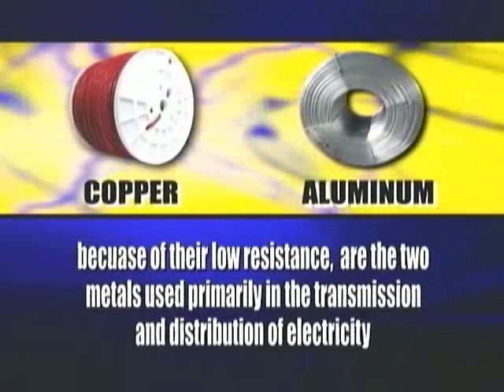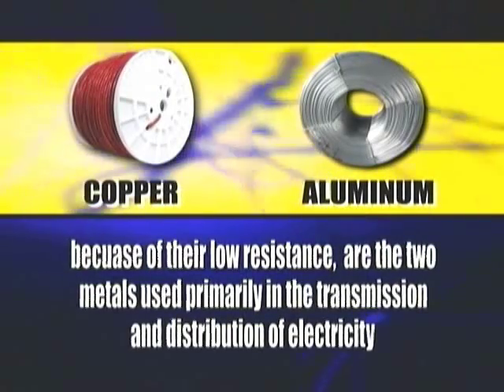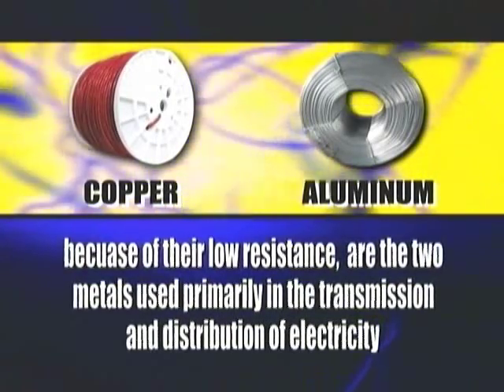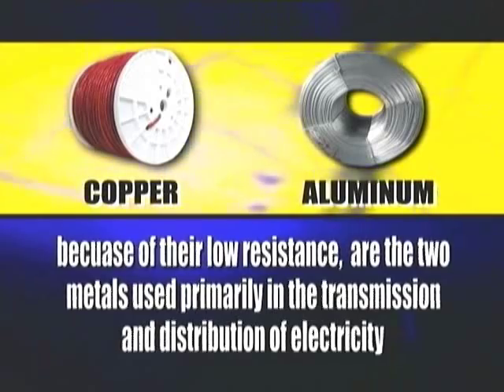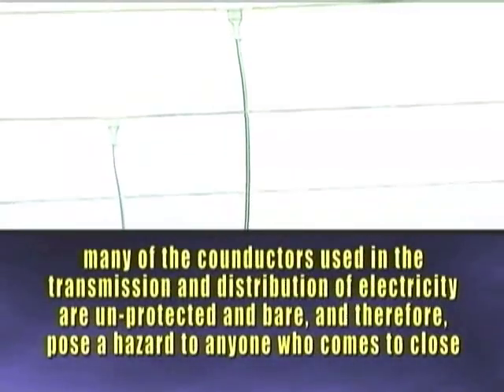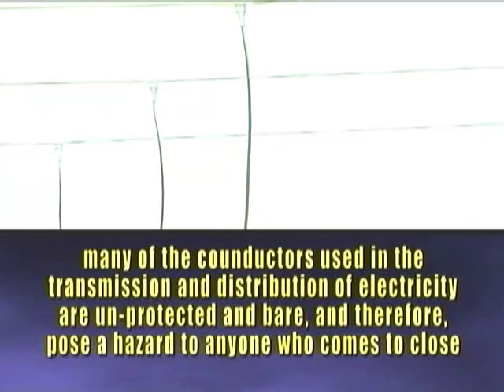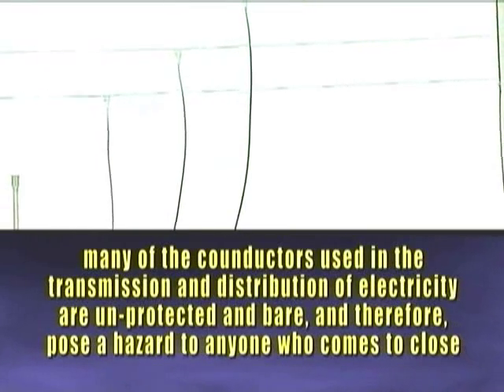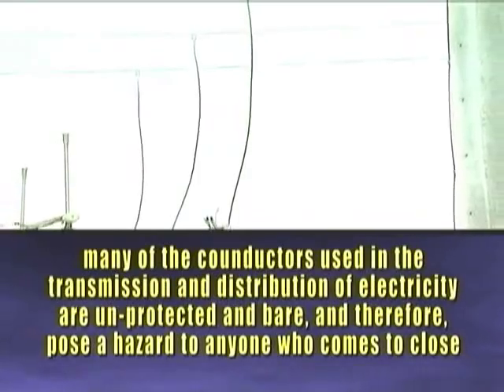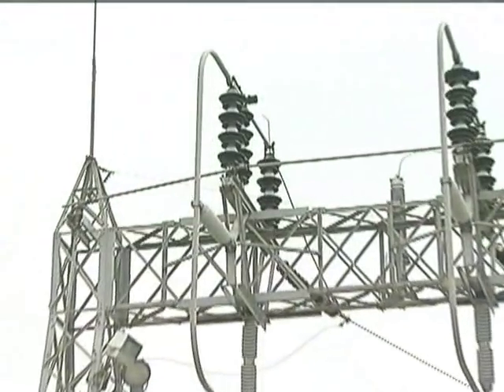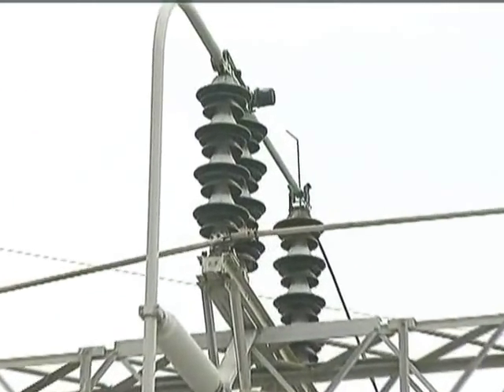Copper and aluminum, because of their low resistance, are the two metals used primarily in the transmission and distribution of electricity. Many of the conductors used in the transmission and distribution of electricity are unprotected and bare, and therefore pose a hazard to anyone who comes too close. These bare conductors are held in place by insulators.